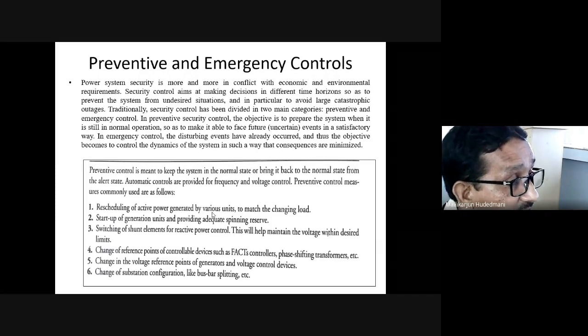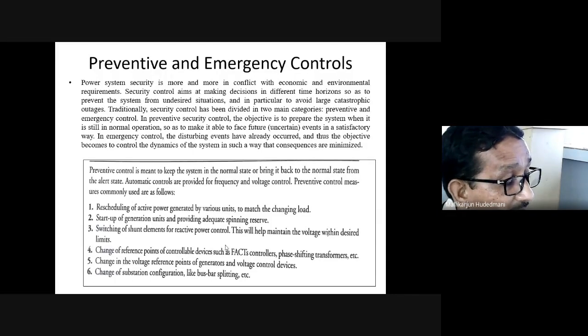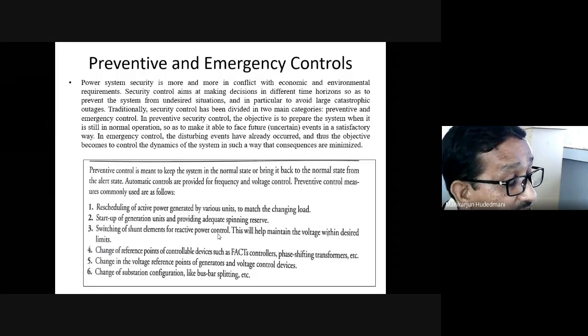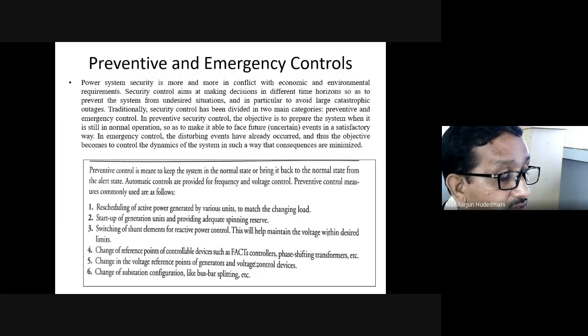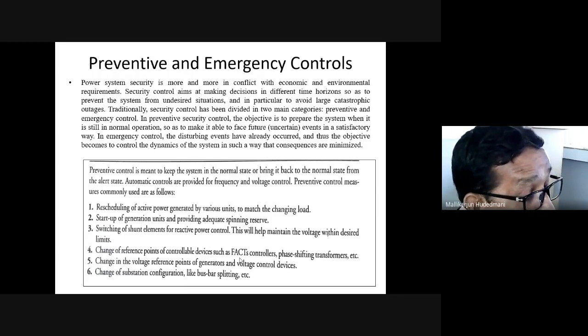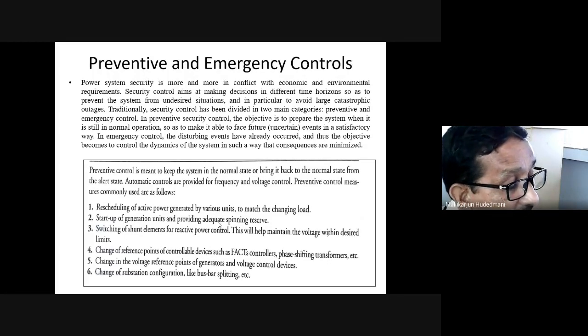If I speak of TCR, thyristor controlled reactor, TSC, thyristor switched capacitor, TCC, thyristor controlled capacitor, like that. So many components are there under the heading FACTS devices. Those devices have to be installed as suitable to their location as required, and their set point needs to be properly tuned so that the changing dynamic load will definitely be counteracted by such a controller. It may be phase shifting transformers, etc. All together come under the reactive power and voltage control.